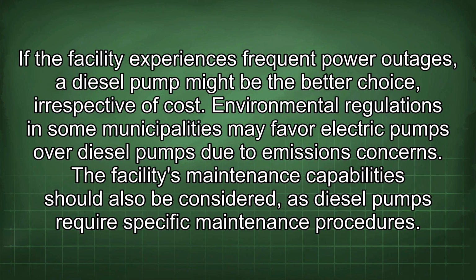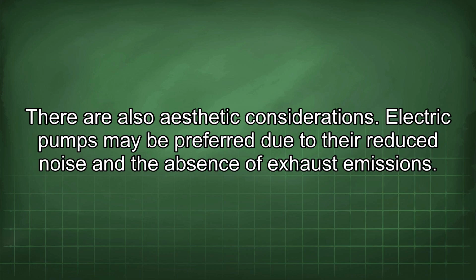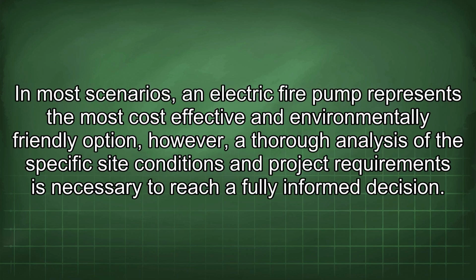Environmental regulations in some municipalities may favor electric pumps over diesel pumps due to emissions concerns. The facility's maintenance capability should also be considered, as diesel pumps require specific maintenance procedures. There are also aesthetic considerations. Electric pumps may be preferred due to their reduced noise and the absence of exhaust emissions. In most scenarios, an electric fire pump represents the most cost-effective and environmentally friendly option. However, a thorough analysis of the specific site conditions and project requirements is necessary to reach a fully informed decision.